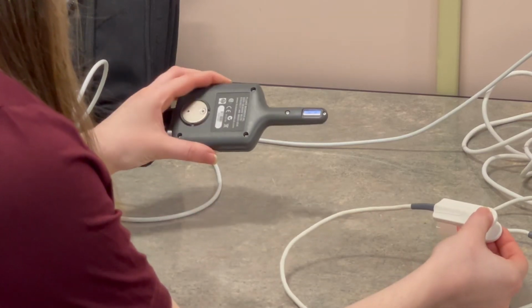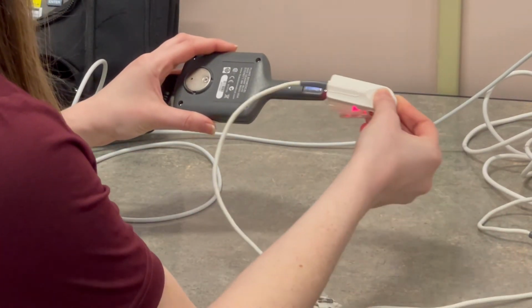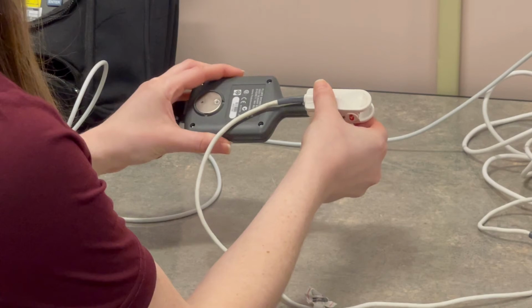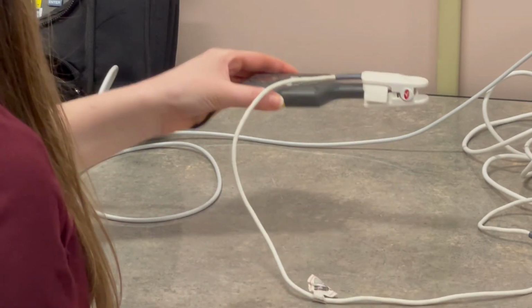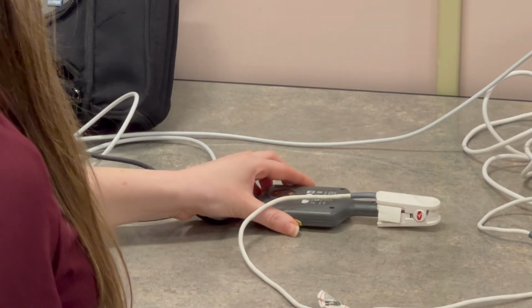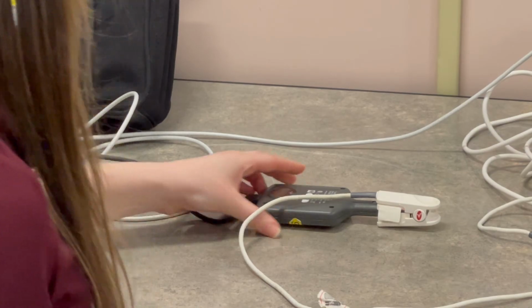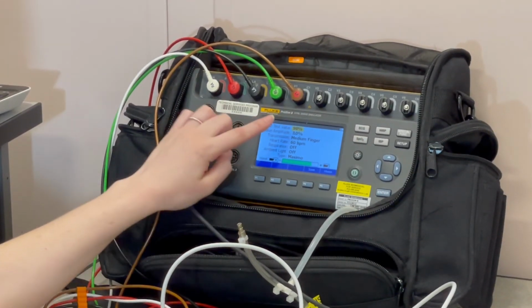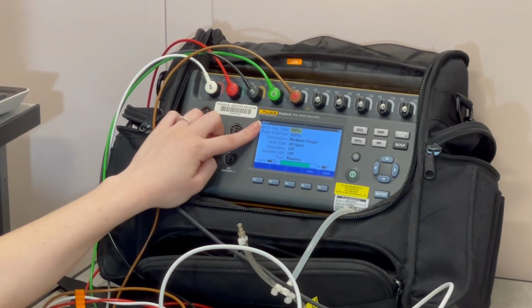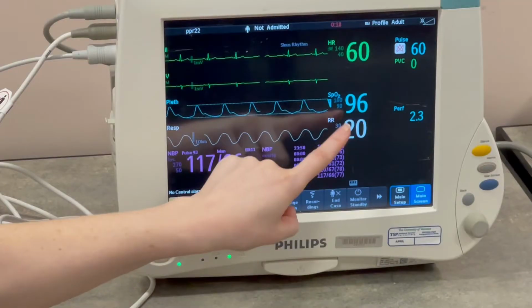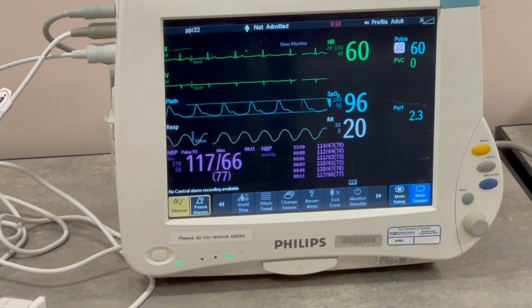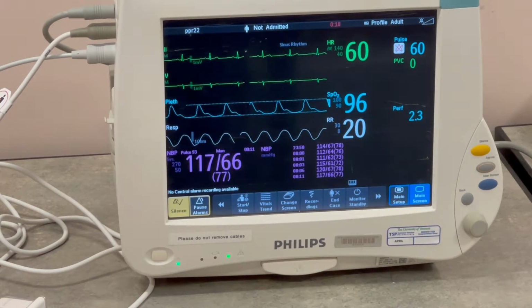Pulse oximetry testing verifies the accuracy of the oxygen saturation measurements and the pulse rate. Specialized test equipment can simulate a variety of oxygen saturation levels and pulse rates. If the specialized test equipment is not available, it may be necessary to test the unit on yourself. If this is done, note your pulse rate manually during the test and compare it against the monitor reading.